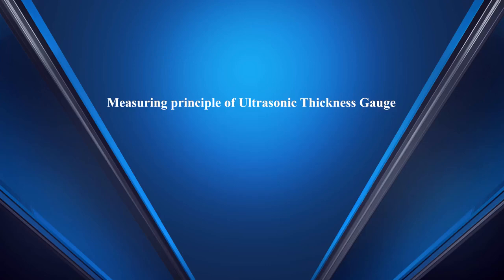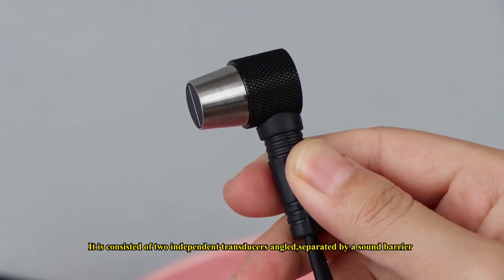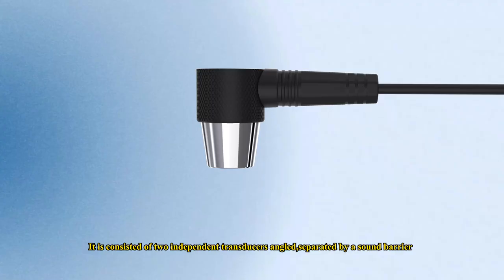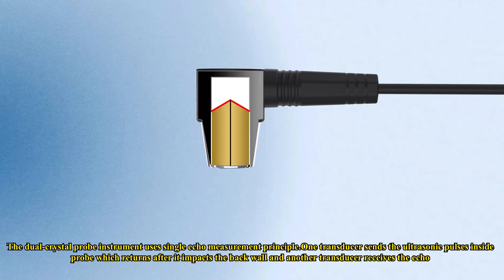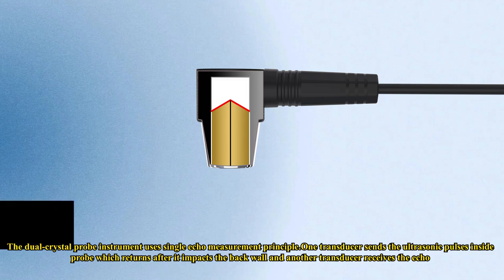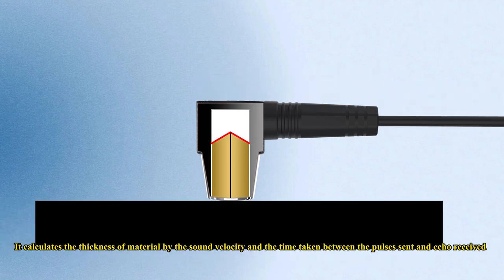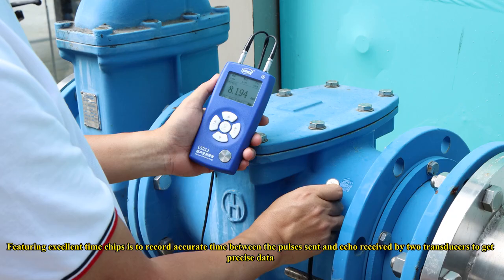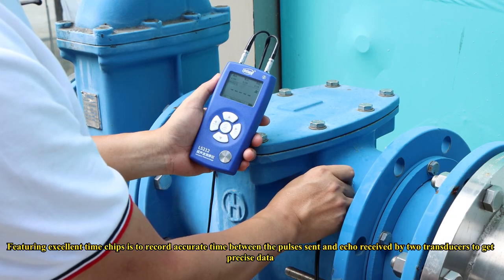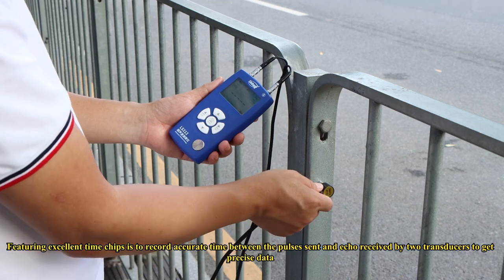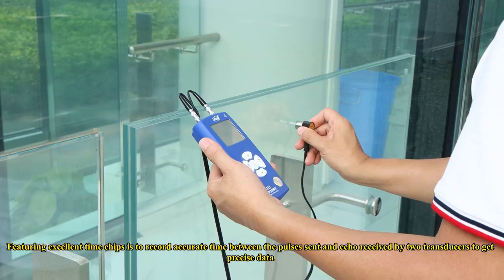Measuring principle of ultrasonic thickness gauge. It consists of 2 independent transducers angled and separated by a sound barrier. The dual crystal probe instrument uses the single echo measurement principle. One transducer sends the ultrasonic pulses inside the probe, which return after they impact the back wall, and another transducer receives the echo. It calculates the thickness of the material by the sound velocity and the time taken between the pulses sent and the echo received. Featuring an excellent time chip, it records the accurate time between the pulses sent and the echo received by the 2 transducers to get precise data.